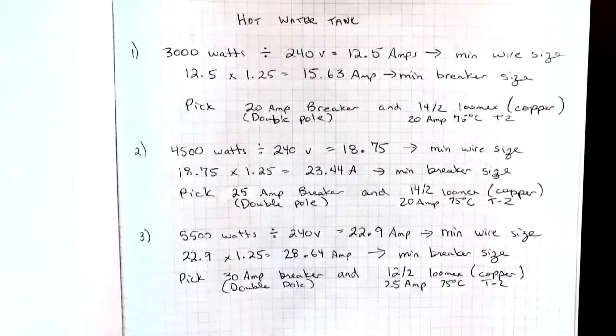It means that each element is 3000 watts, but they can never come on at the same time. So when we're calculating our wire and breaker size, we use just the wattage of one element.